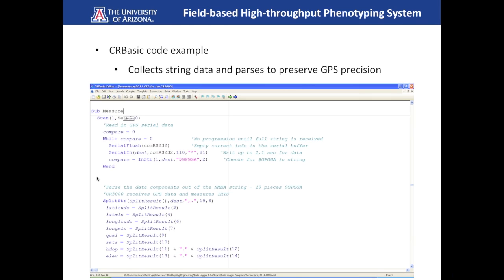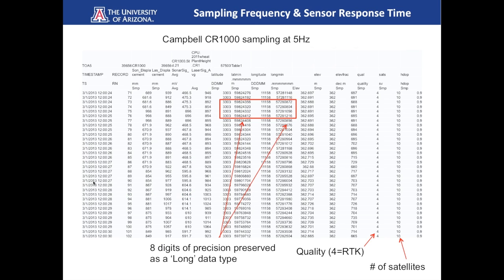So I have to deal with Campbell's own data types, for those of you who are familiar with programming. In order to overcome that problem with the data types cutting off 2 digits of precision, because if you try to parse it out and save it as a decimal, it ends up cutting off 2 digits, and those 2 digits are what get us into the centimeter level precision. So that was a pretty important thing to do in order to keep all those 8 digits. What we did was break it up in a way where we save all of those numbers as whole numbers, as integers, so that we can keep all of the digits that are available, and then we just put them back together in post-processing, which is a really simple procedure.